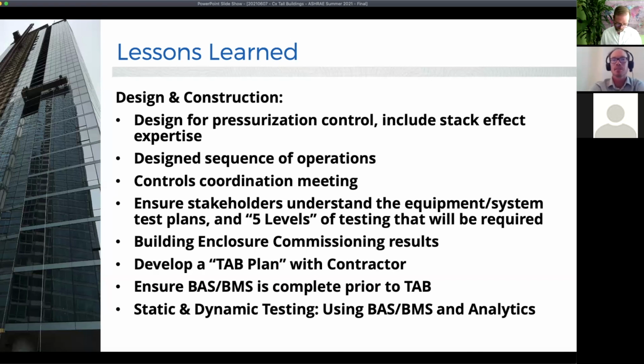But that moves into level 4, and that's where Ben and I get heavily involved, and we write test plans for. So level 4 is functional testing, and that's the heart of what we do. We're going to verify, we're going to make some adjustments, we're going to work hand in hand with the controls contractor, the mechanical design team, balancing contractor, and we're going to verify that these systems actually perform.